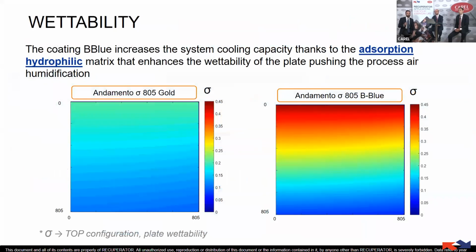Now let's focus a little more on this coating. This coating is special because it is hydrophilic and also absorbent. It is able to retain the water on the surface, so we can increase the wettability. We can create an even film of water on the whole surface, decreasing the temperature of the system, and in this way we increase the cooling capacity. In this picture we show the wettability of the plate. With the gold, we have a wettability value that is half of the wettability of the blue, because of the hydrophilic and absorption characteristics.